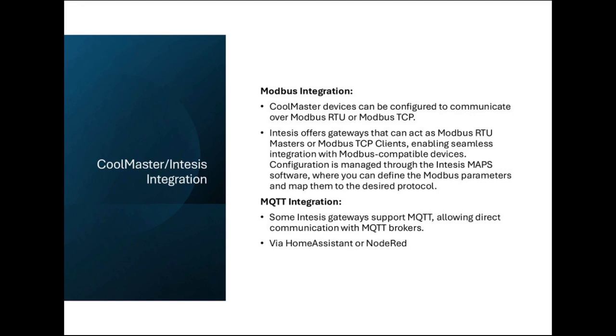So we discussed different scenarios. One is direct HVAC control using GRT3 iNELS units like GRT370, iNELS actuators, and fan coil units. Second, we discussed the Modbus protocol, so we have RFTC3, GRT300, and CU310 Modbus for Modbus integration with third-party HVAC systems that support Modbus. And then we have Intesis, different options, Aircon Gateway, also add-on. And then finally, through MQTT integration.